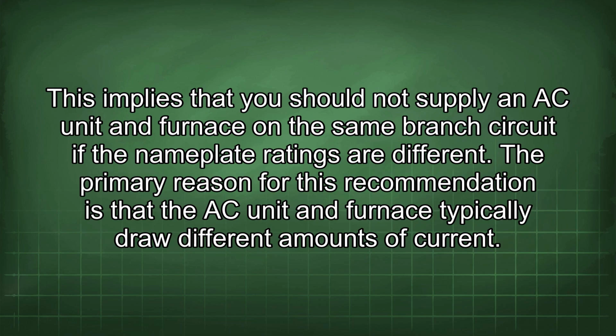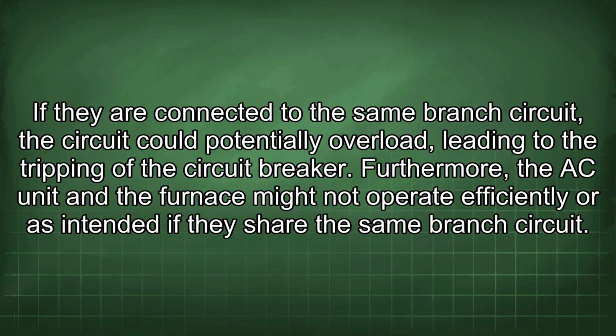This implies that you should not supply an AC unit and furnace on the same branch circuit if the nameplate ratings are different. The primary reason for this recommendation is that the AC unit and furnace typically draw different amounts of current. If they are connected to the same branch circuit, the circuit could potentially overload, leading to the tripping of the circuit breaker. Furthermore, the AC unit and the furnace might not operate efficiently or as intended if they share the same branch circuit.